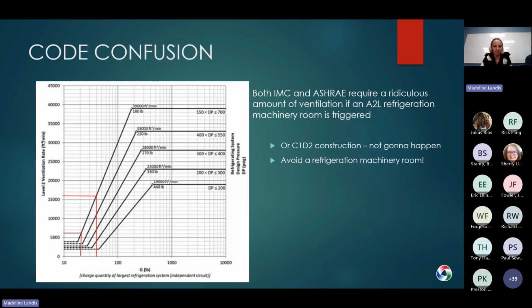And the other thing that both codes trigger is a hellacious amount of ventilation air if a refrigeration machinery room is triggered. Now, there's an option to go with a C1D2, essentially quote unquote explosion proof construction in the room, but that's not going to happen. So you really want to avoid a refrigeration machinery room. Even when replacing an existing machinery room, the old A1 ventilation rate is going to be a fraction of what you're going to need for a comparable A2L refrigerant.